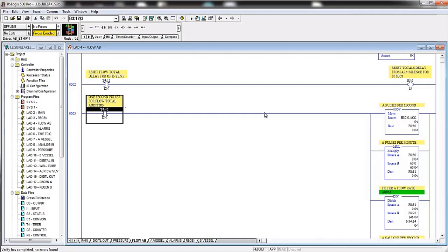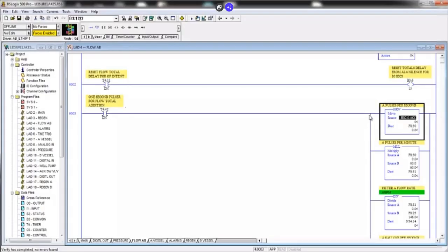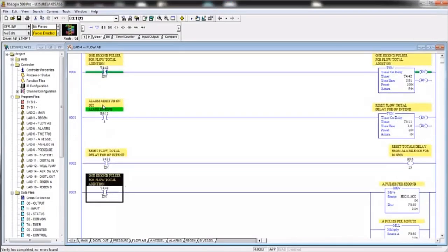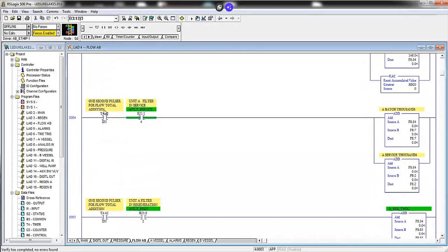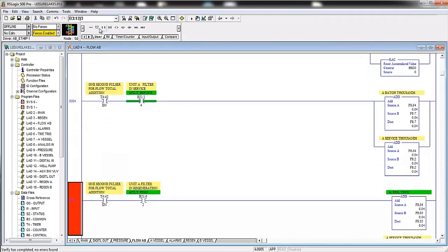That's great. The program loves that. Not a problem. But actions have to be on separate branches. Just remember, one action per branch, conditions on the left, actions on the right. And if every condition that's lined up on the left is not true, what happens on the right will be skipped, and it'll proceed to the next rung.